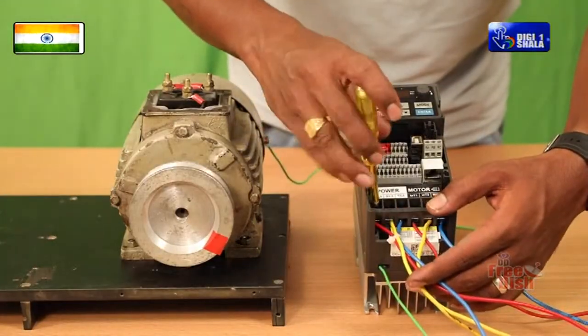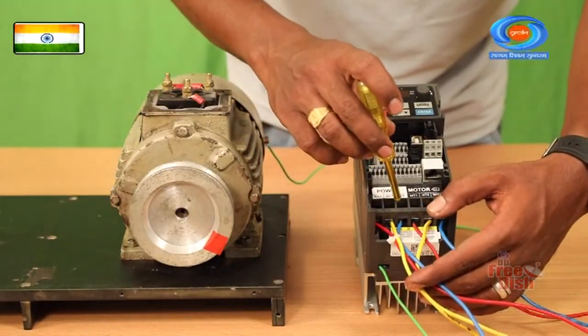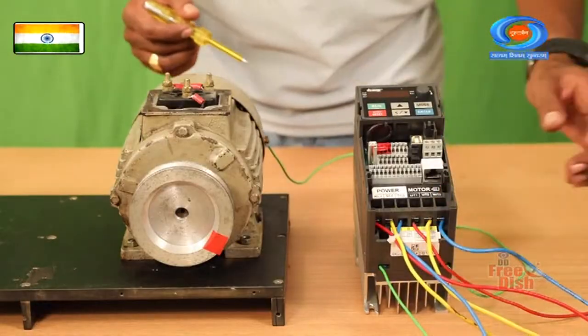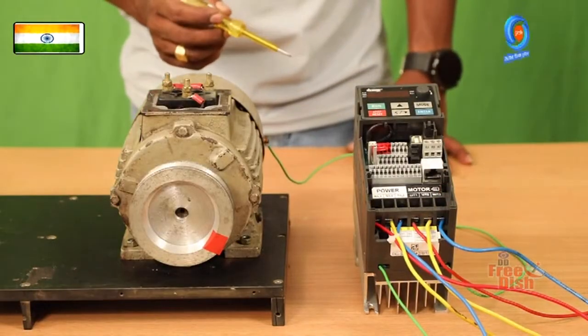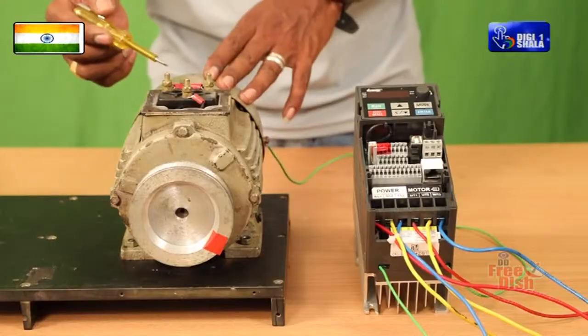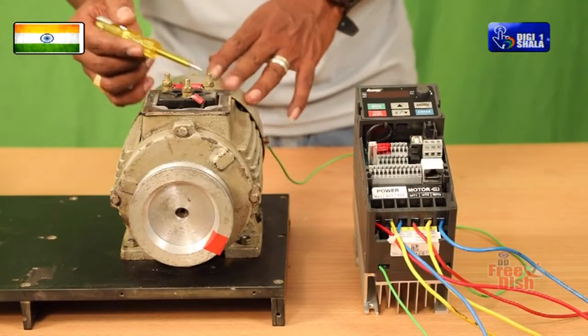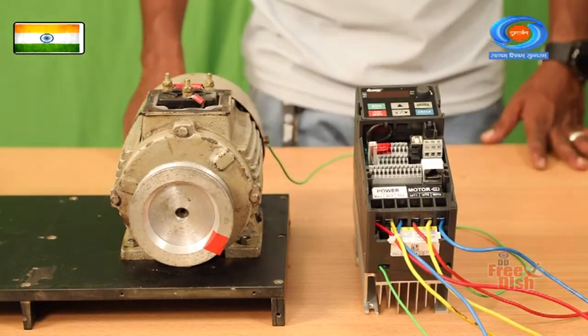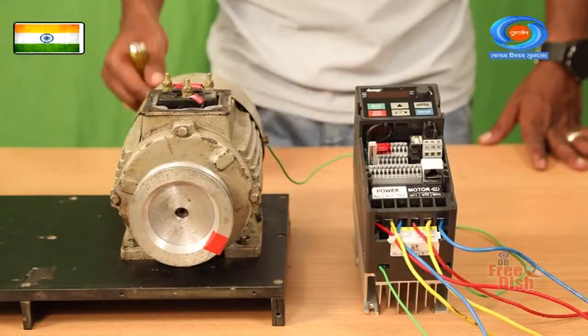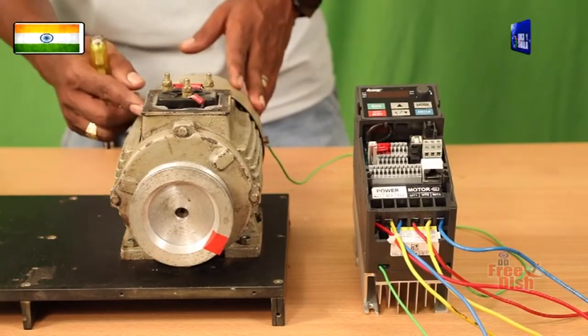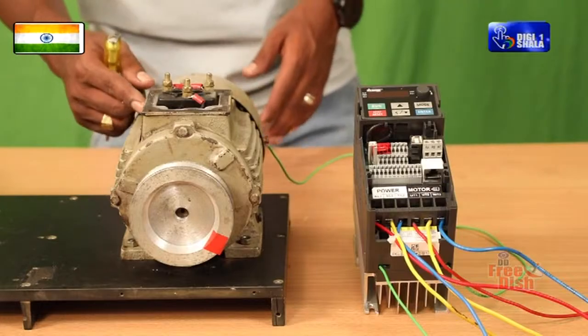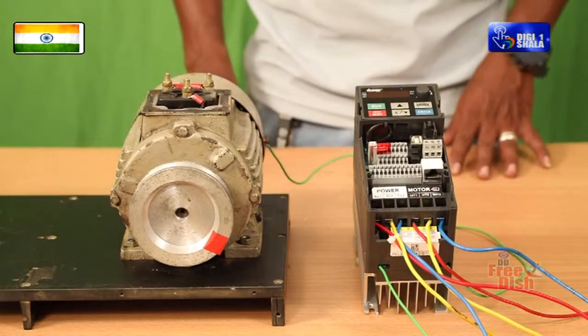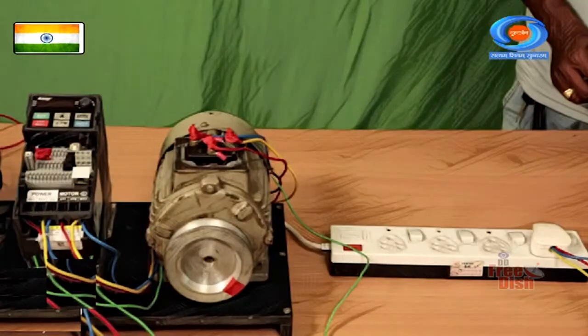Control wiring. Connect any control wires necessary for operations such as start or stop signals or speed control signals according to the specific requirements of your application. This may involve connecting wires from control devices such as a PLC or control panel to the appropriate terminals on the AC drive. Connect the motor, AC drive, main switch as per approved diagram.